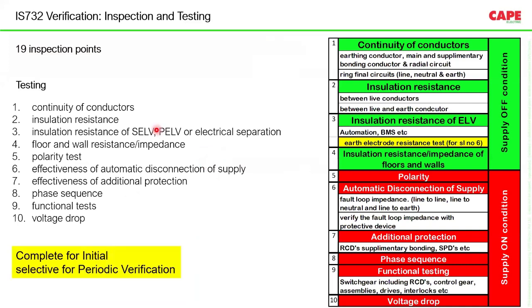IS732 recommends 19 inspection points in part 1, section 17, and there are 10 tests included in IS732. These 10 tests we explained last time, and we are also explaining them in several programs. It starts with continuity of conductors, then insulation resistance of low voltage and extra low voltage, and insulation resistance or impedance of floors and walls is one of the tests. It is just to find out whether the floor or the wall is in a dangerous situation to create a shock. Then test number 6, automatic disconnection of supply.